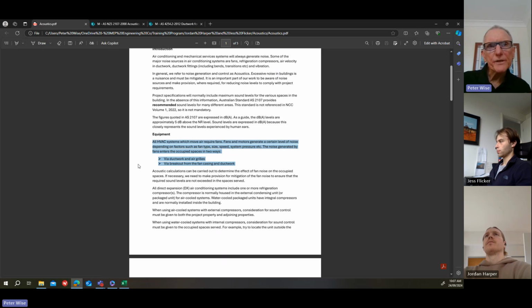Some of the noise that's in the ductwork can actually break through the casing of the fan and the ductwork and create noise issues. But generally, that's not our main problem. The main problem we've got to deal with is through the ductwork and the grills. But there is another one, which is vibration. And I'll talk about that a bit later.